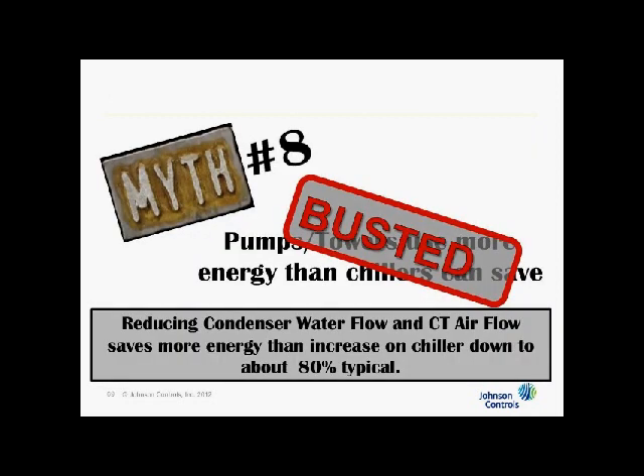And that means that myth number 8 is busted. Reducing condenser water flow and cooling tower airflow does save more energy than the increase in energy on the chiller, down to about 80%. Now, if you go too far, then yes, it will increase. But we found that there is an optimum condition.